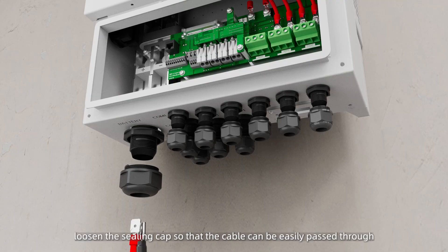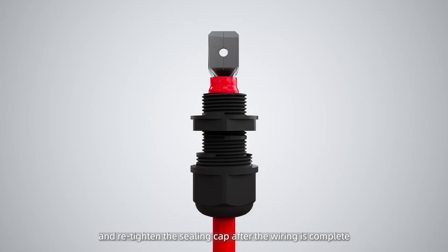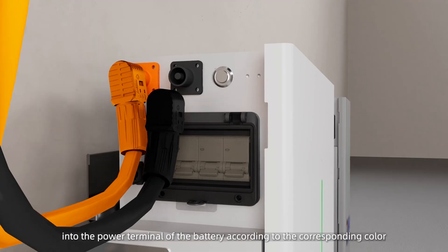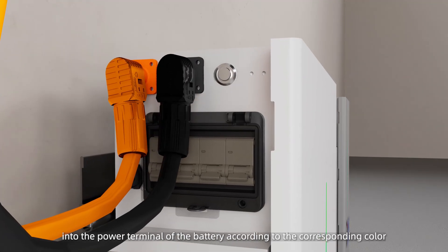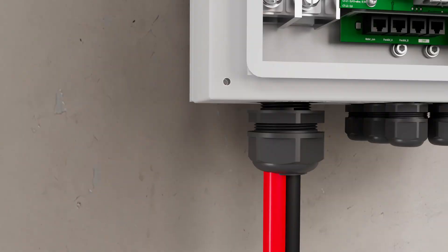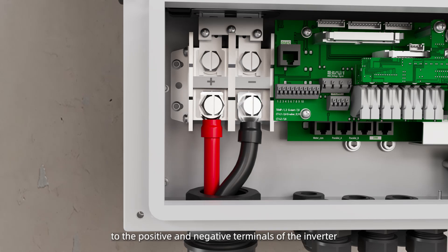When wiring, loosen the sealing cap so that the cable can be easily passed through and re-tighten the sealing cap after the wiring is complete. Plug the end of the power cable with a quick plug terminal into the power terminal of the battery according to the corresponding color. Connect the other end of the power cord to the positive and negative terminals of the inverter.